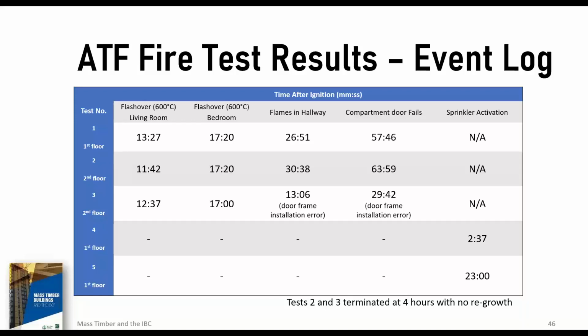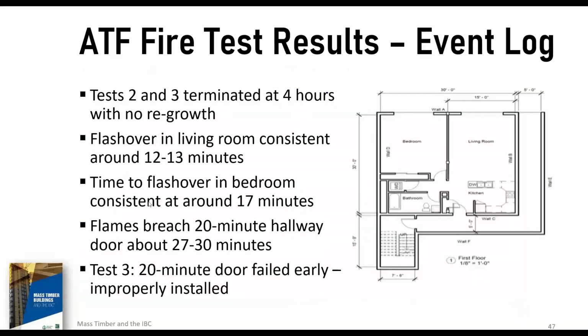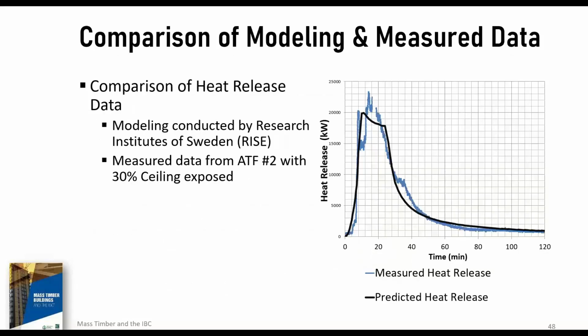Sprinkler activation at 2 minutes and 37 seconds extinguished the fire, as well as charging the standpipe, in test number 5. The fire was out at 23 minutes, or started to go out at 23 minutes. It took a couple minutes for the sprinkler system to bring the fire under control. Some timeline there, we talked about that, flashover times, right at 17 minutes for the bedroom. And we talked about the breaches of the compartment door and the installation error on test 3 for the 20-minute door. No compromise and no failures with the 90-minute rated door at the corridor associated with the stairwell at the end of the hall.